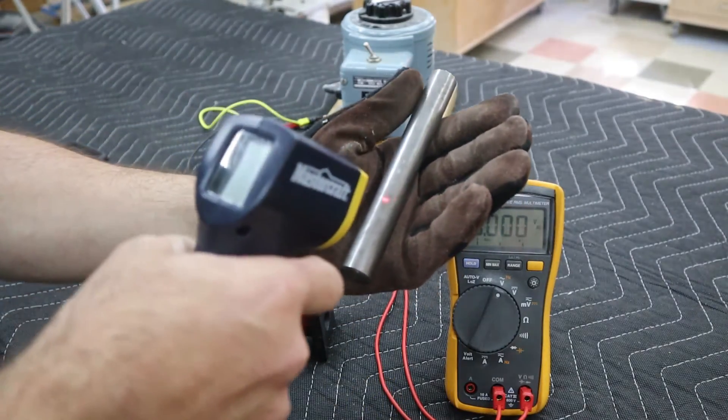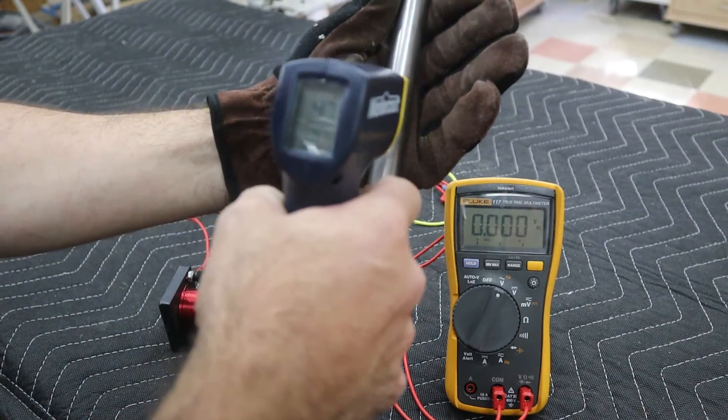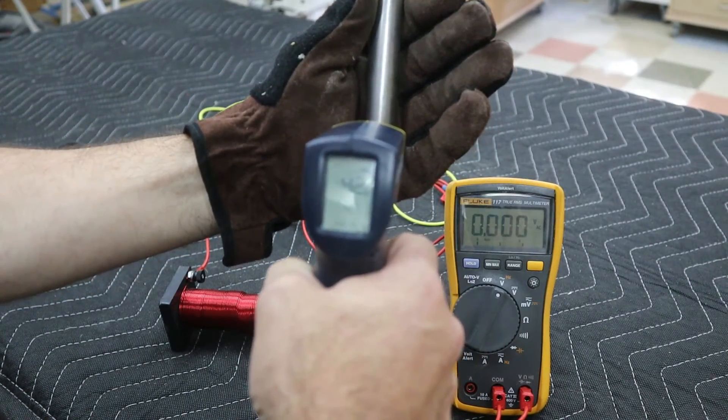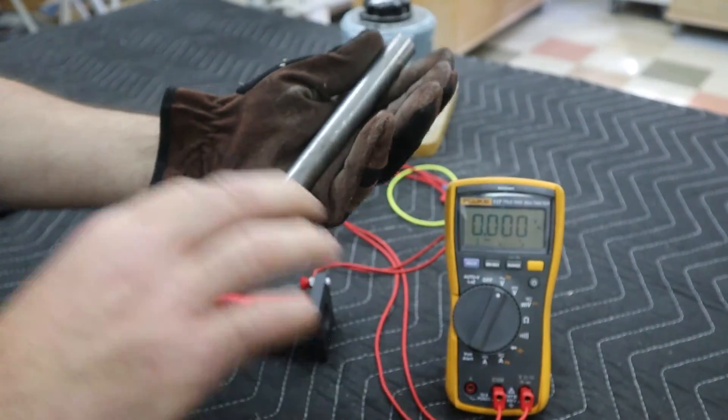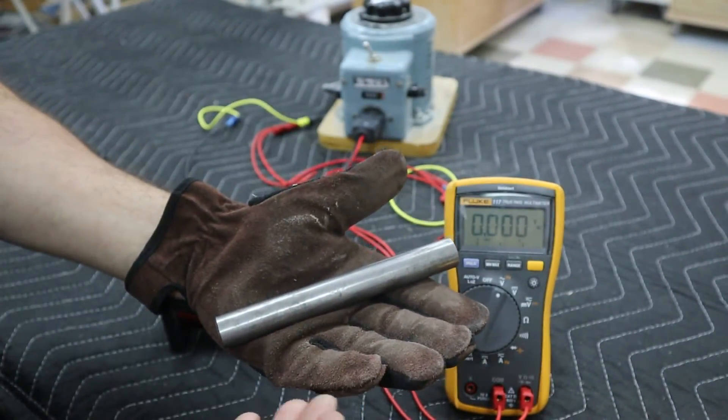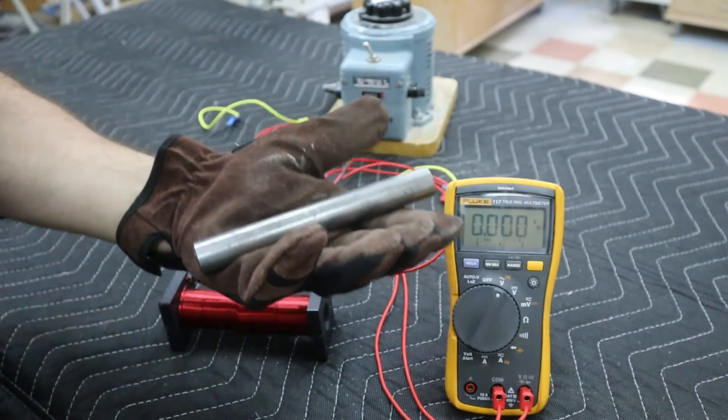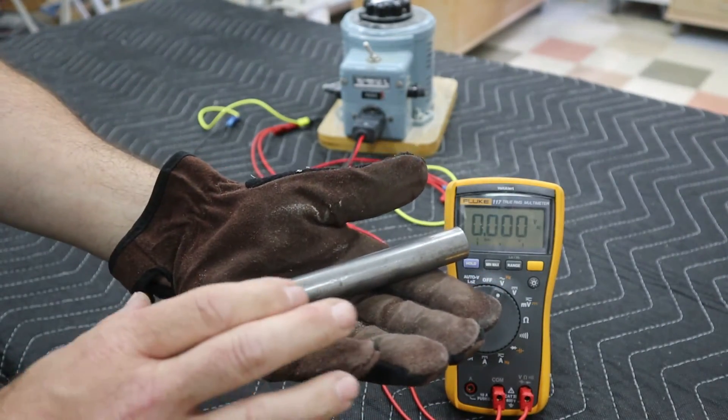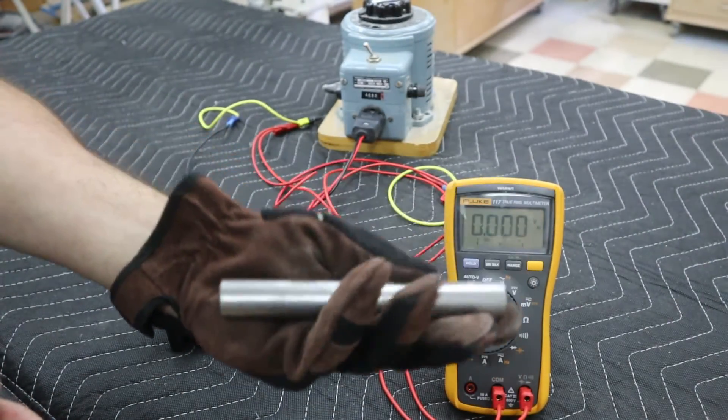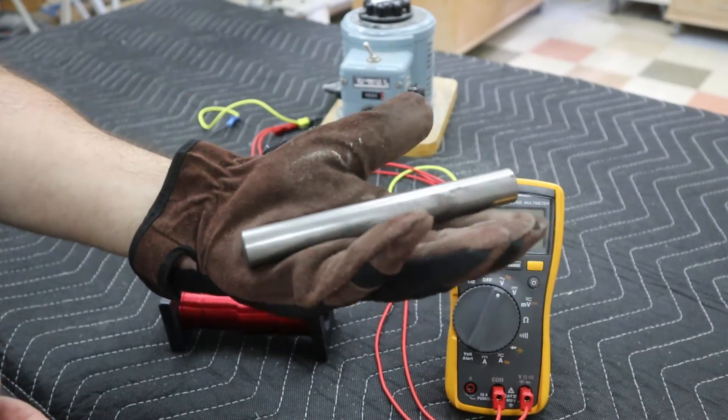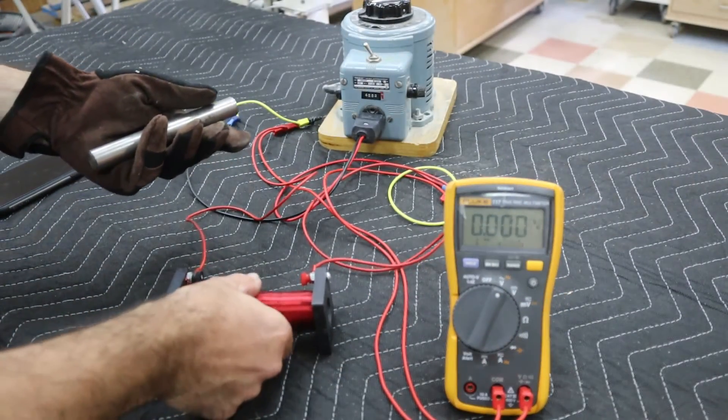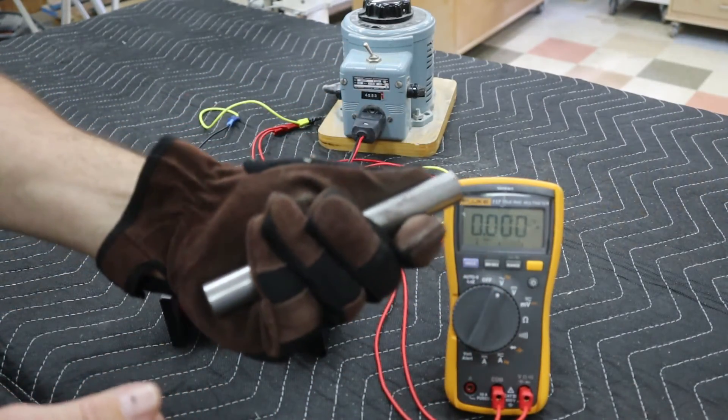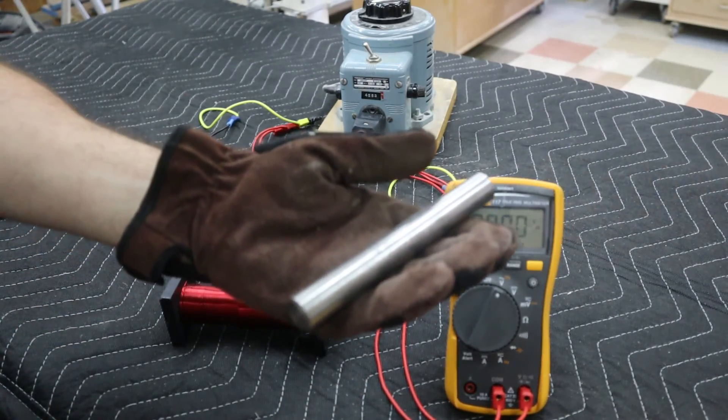In trying to demonstrate the effects of an AC magnetic field that is constantly reversing, what you have are eddy currents. Eddy currents have a very harmful effect on equipment that is not laminated. Here's proof positive—we are using a solid steel bar and we didn't even have it on for a full five minutes, and it started to heat up this steel bar to the point where I can't touch it with my bare hands.